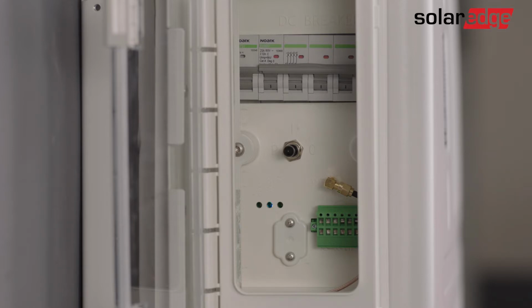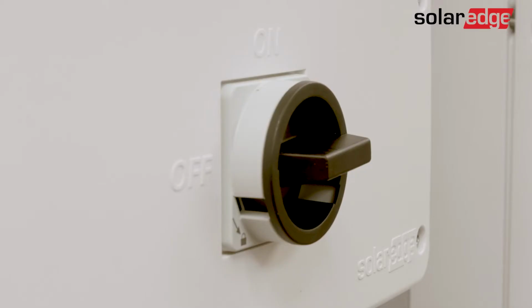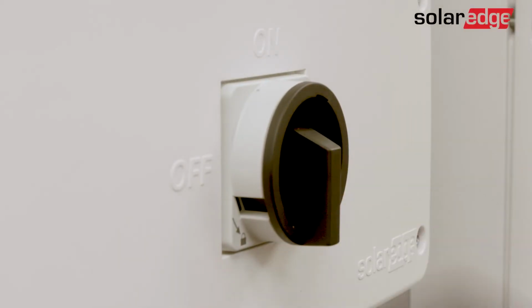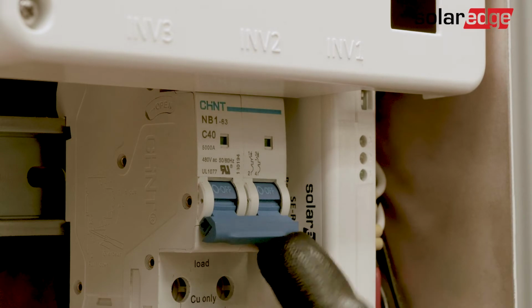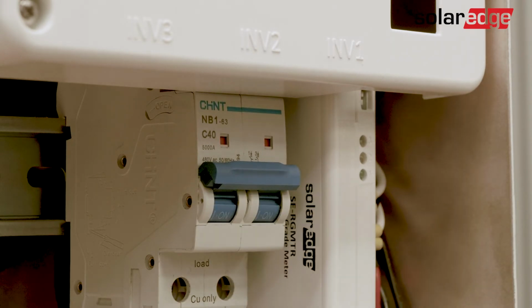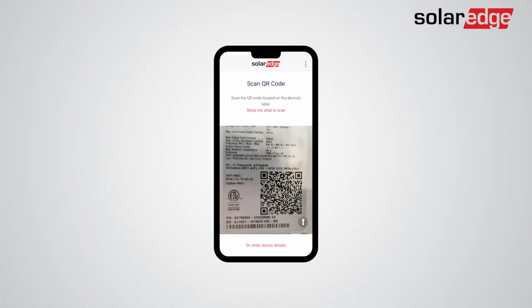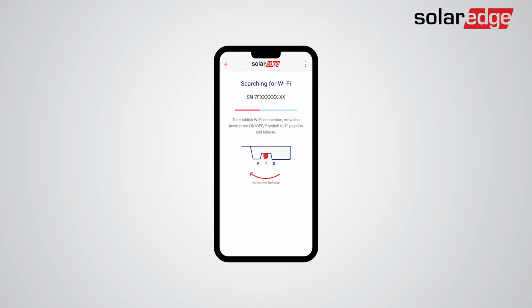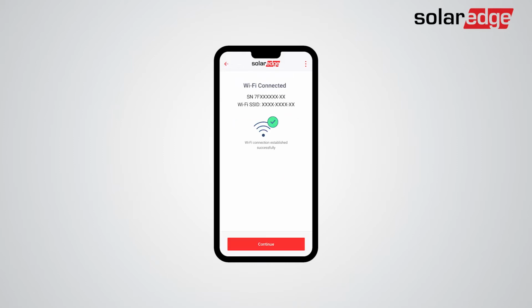Finally, before connecting with SetApp to the inverter, if there is a DC switch on the inverter, it should be on. Make sure that the inverter is connected to AC. Now, launch SetApp and scan the QR code on the inverter. Connect to the inverter by switching the on-off P switch on the inverter to the P state for 2 seconds. Follow the on-screen instructions until you reach the inverter commissioning screen.